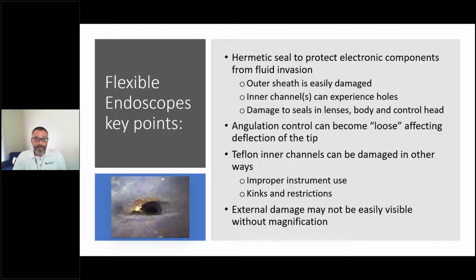Risks are: the outer sheaths can be damaged, and it doesn't take a whole lot. The inner sheaths and inner channels can have holes, gouges, and damage. And of course there can be damage to the seals in the lens, the body, and the control head. So remember, when doing leak testing, you're not only checking the distal tip and the deflection, but when moving it through its whole range, you're also checking the dials, because those are sealed as well.